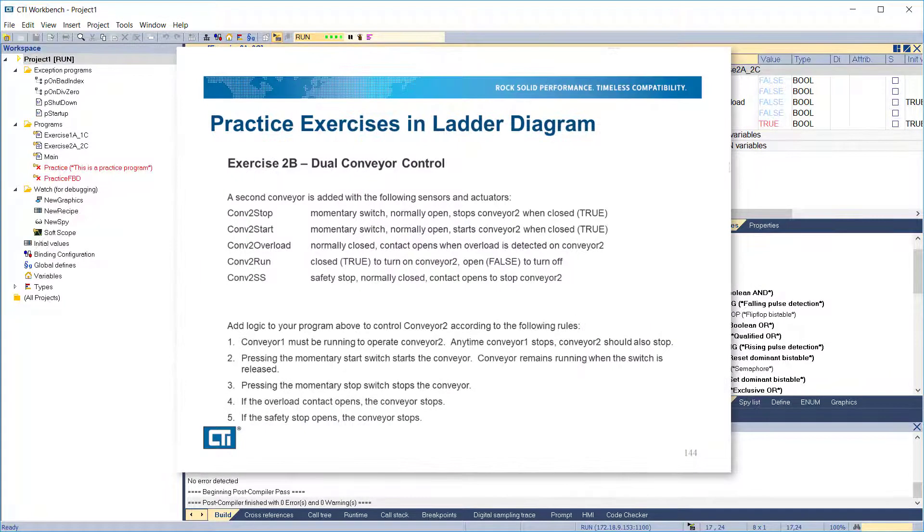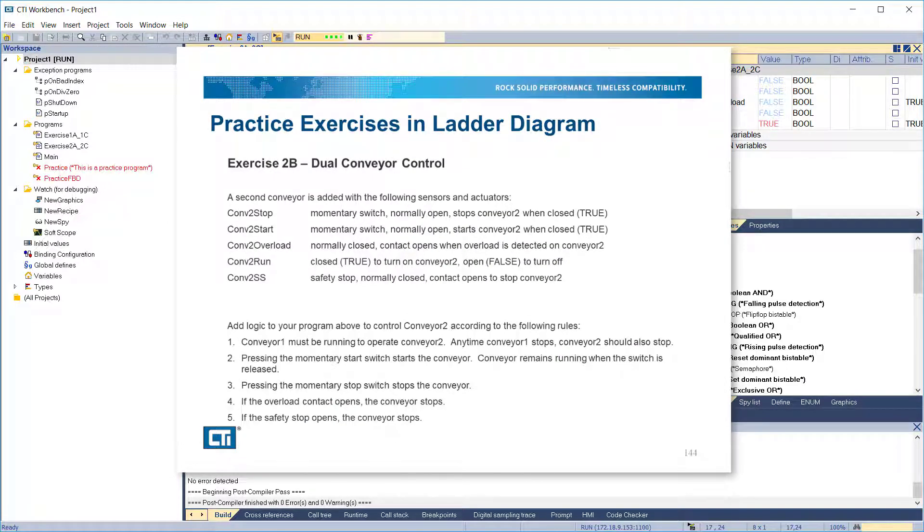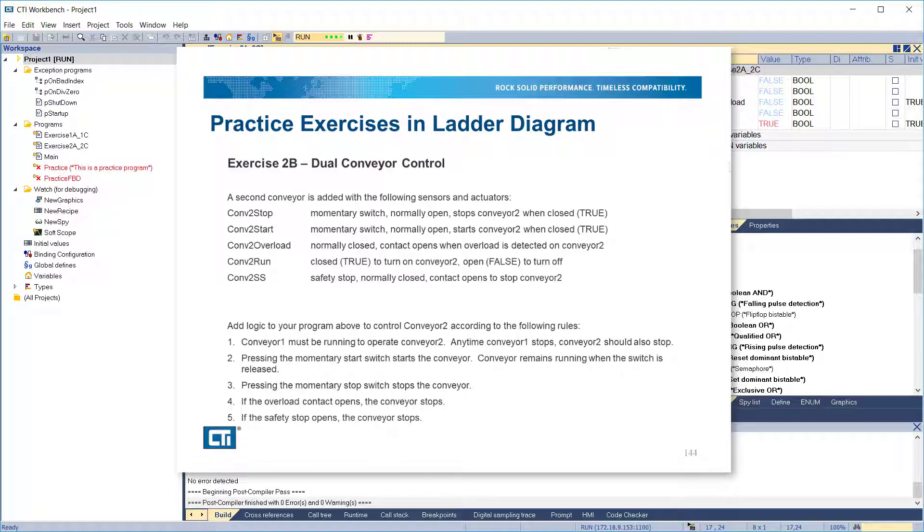In exercise 2b, we'll add a second conveyor with an identical set of sensors and actuators. Then add logic to control conveyor 2 according to the following rules: Conveyor 1 must be running to operate conveyor 2. Any time conveyor 1 stops, conveyor 2 should also stop. Pressing the momentary start switch starts the conveyor. The conveyor remains running when the switch is released. Pressing the momentary stop switch stops the conveyor. If the overload contact opens, the conveyor stops. If the safety stop opens, the conveyor stops.